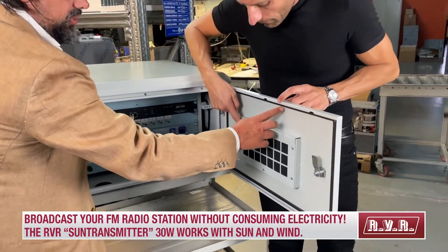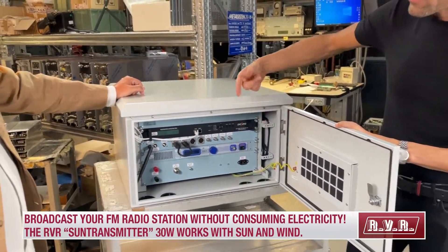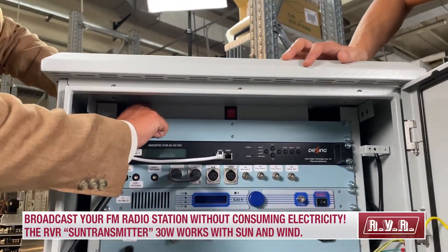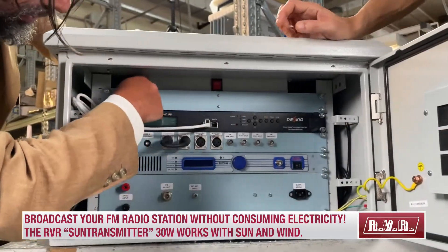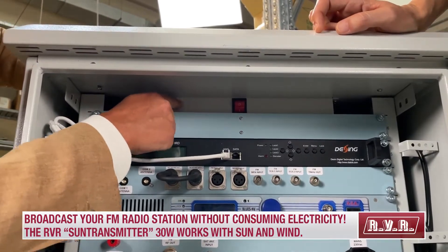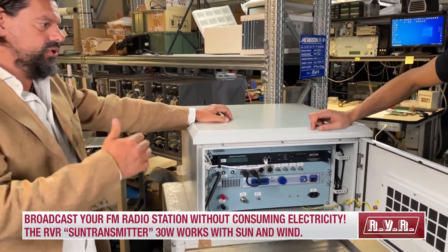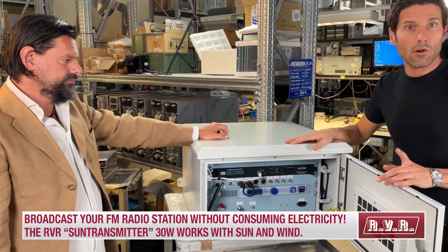The unit is fully sealed to keep water and everything outside. It has an air filter, and for cooling there is a panel with four fans used to circulate air from the intake on the front door, rejected laterally. The fans are oversized and redundant, providing enough air circulation to keep the system running up to 60 degrees Celsius.